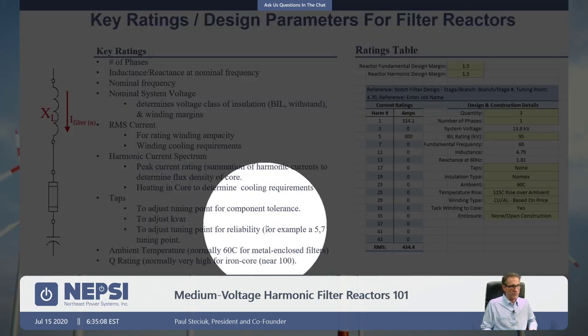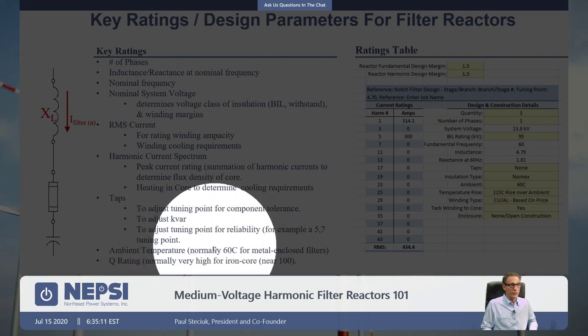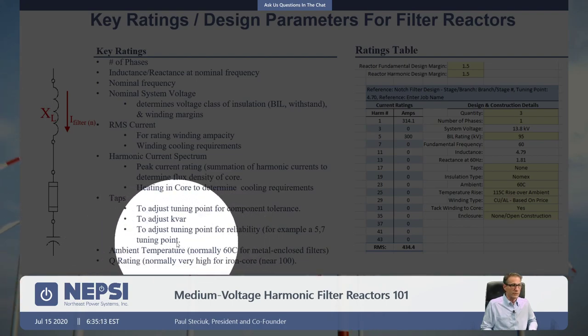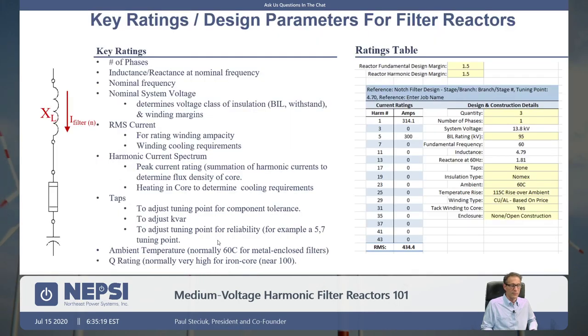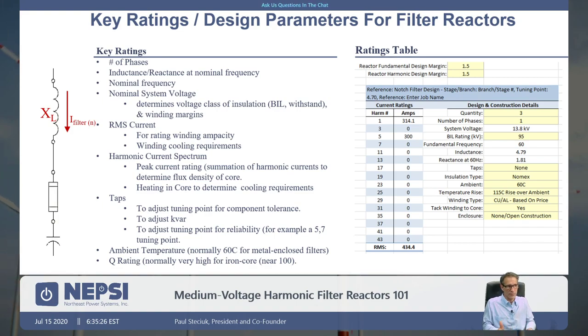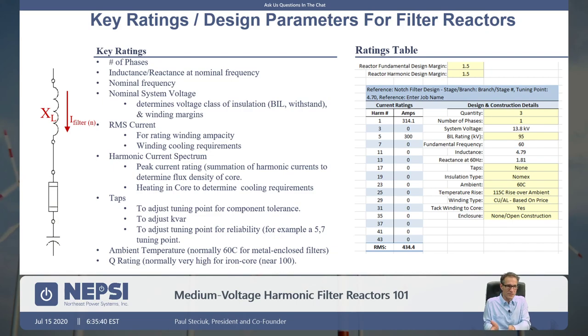Ambient temperature — you have to specify what the ambient temperature is. We talked about ambient temperature in metal-enclosed cap banks and filter banks and the concept of specifying 60°C. It may be that outside the enclosure is 40°C, but inside the enclosure is 60°C. We often see specifications written around a 40°C ambient. But if you are purchasing reactors or writing a specification that includes a reactor sitting inside the enclosure, it should be specified as 60°C, not 40°C. To specify 40°C would be to create a less reliable system.